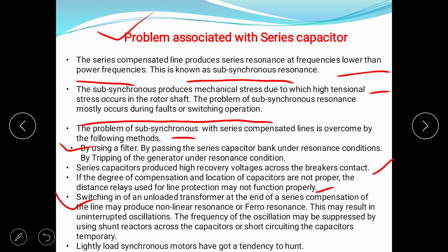The line may produce non-linear resonance or ferroresonance. This may result in uninterrupted oscillations. The frequency of oscillation may be suppressed by using shunt reactors across the capacitor or short circuiting the capacitor temporarily. Next, lightly loaded synchronous motors have a tendency to hunt, meaning there is a problem of hunting.